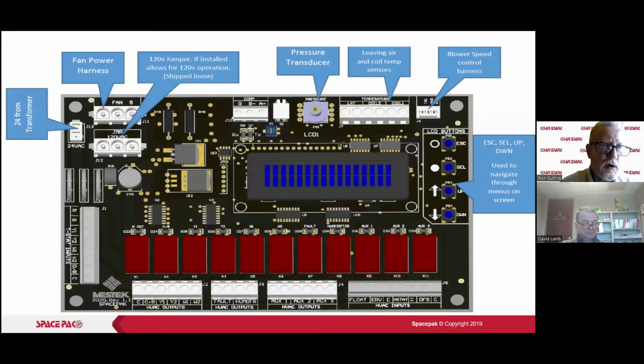All right, so 24-volt hookup to the right there. Our fan harness plugs in right there where it says fan. Our jumper for 120-volt operation comes shipped loose with the unit. So if you do want to use 120-volt, then follow the directions to use that jumper. It's very easy to do with that jumper. We've got the pressure transducer. All right, so we've got a plastic tube, like we use on a manometer, running from the pitot tube at the outlet of the unit over to this pressure transducer. Make sure that tube is not kinked, bent, etc., so that we're getting a good reading on the air pressure at that pressure transducer.